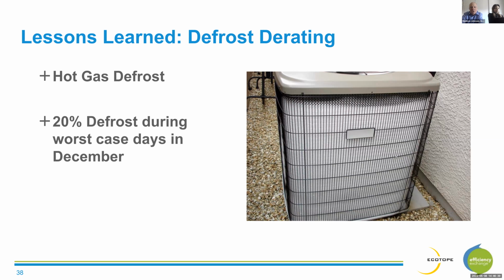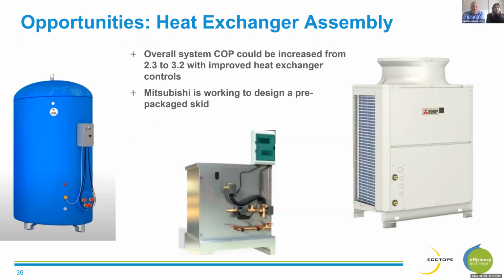One interesting one is that you have to take into consideration when sizing these Mitsubishi products that 20% of the time during the worst case hours, when it's humid and cold outside in December, it's going to be in defrost and not making hot water. So systems need to be about 20% bigger in our climate to account for that defrost time.